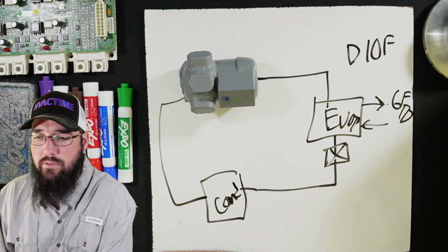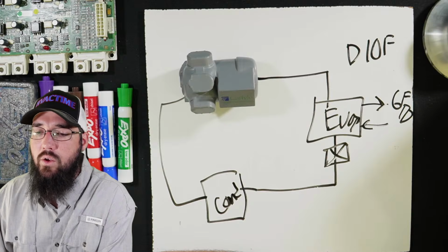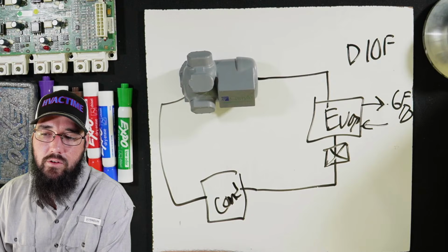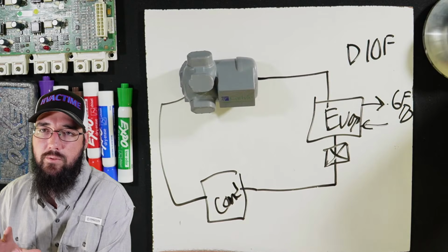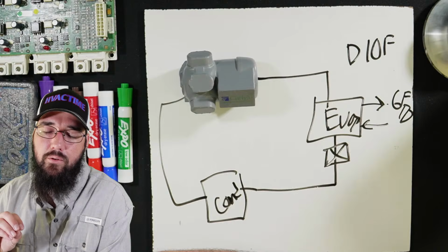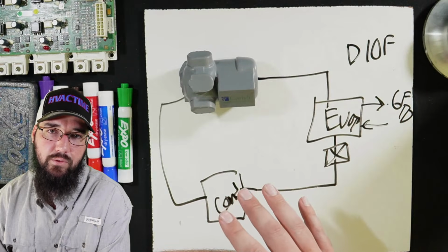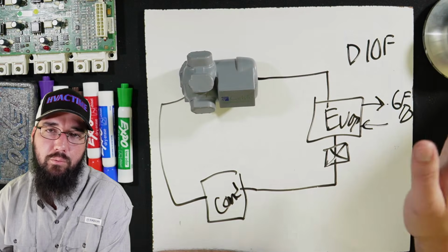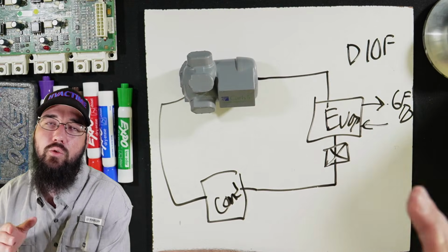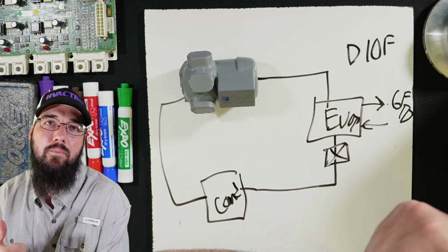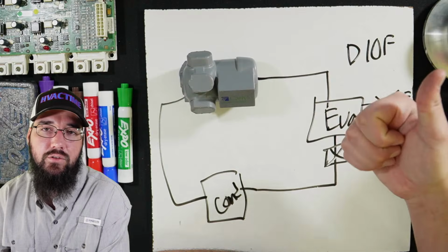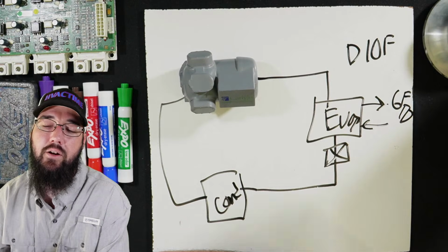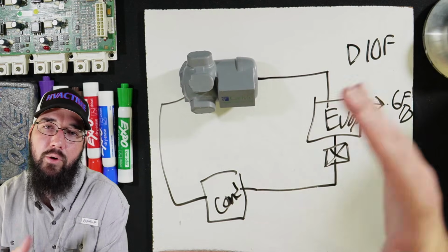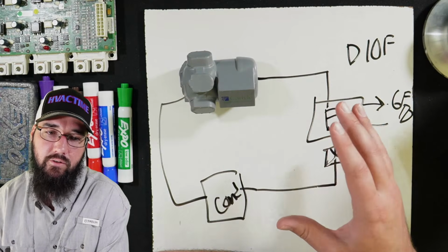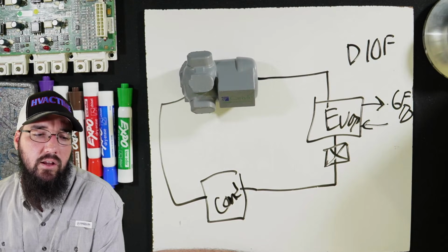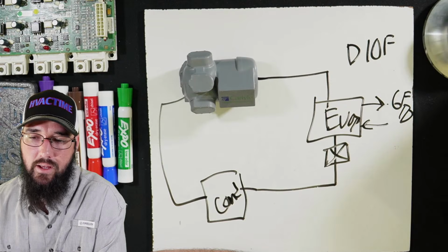I guess that's why they prefer having two circuits at reduced load rather than one circuit alone. Well, so now you're getting into staging strategies, okay? And there are different concepts to these strategies. Be careful not to get too far off into other concepts, right? So when do we go from two compressors to one compressor, or from two circuits to one circuit in our staging sequence has a lot to do with minimizing starts and balancing load. And sometimes it is better to have two compressors unloaded versus one compressor, but at some point there's a breakover there, and that's a very complex conversation in and of itself. It would take a lot of working through to really explain all of that in detail.